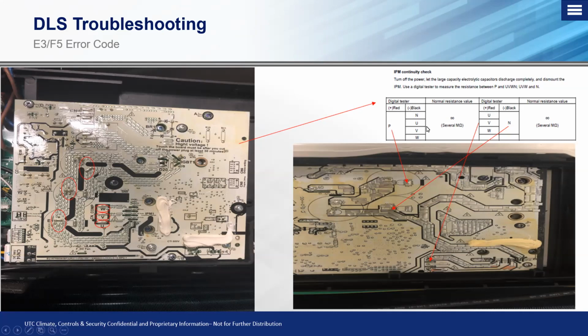The same process applies on the single zone, or a single board, I should say, but it's not as straightforward as the split type boards. Now you see on here, there's no markings. So what I tell guys to look for is the actual indentations of where your capacitor buses are, because they still will have those two posts that stick out of here. Okay, so you want to go between your positive with your red lead, and then you want to find where those connections are on the underside of the board, whether you're dealing with an outdoor fan motor or a compressor. So the same rule applies.